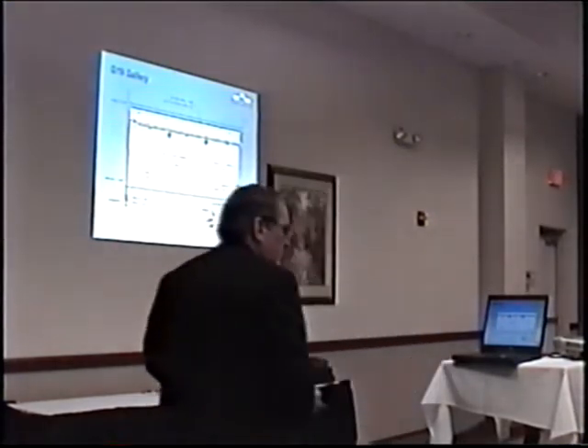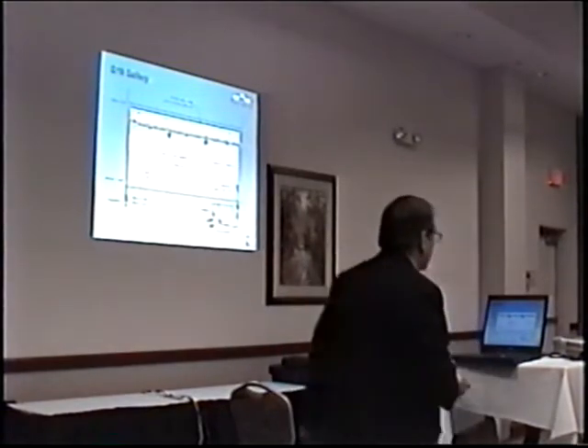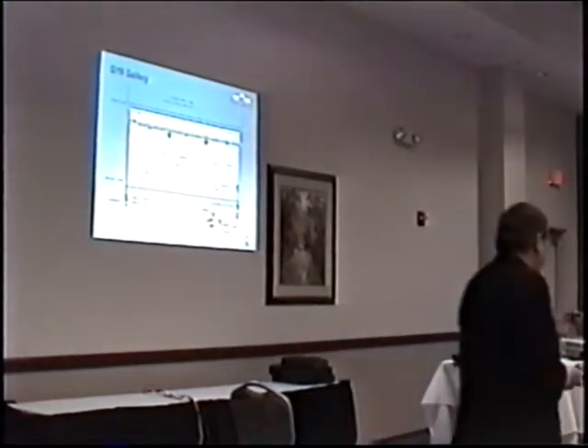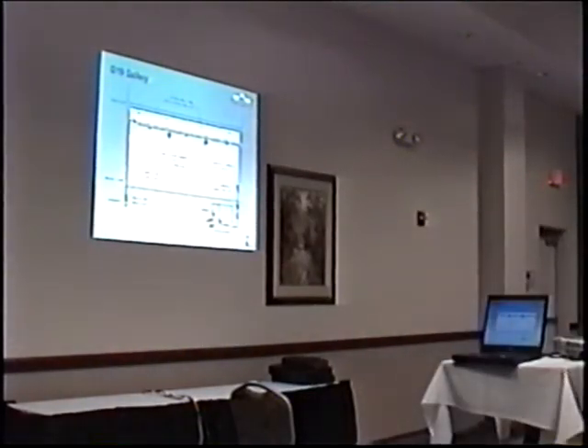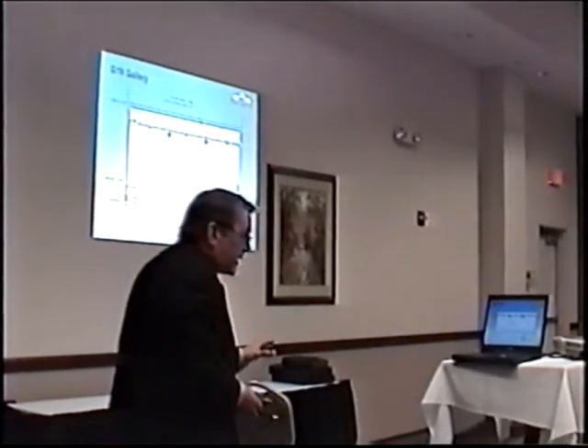Quick question. Are all those nozzles going to discharge water at one time based on a detection system, or individual nozzles? They are individual nozzles. Machinery spaces have open nozzles. These are thermally activated nozzles, 2.5 millimeter glass bulbs. You can pass that around. So they're just like a sprinkler.